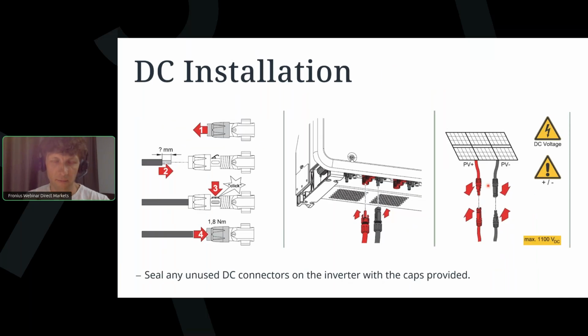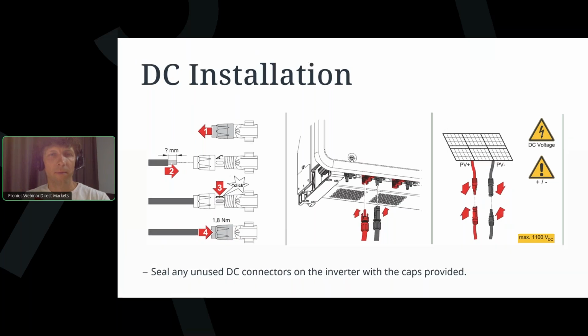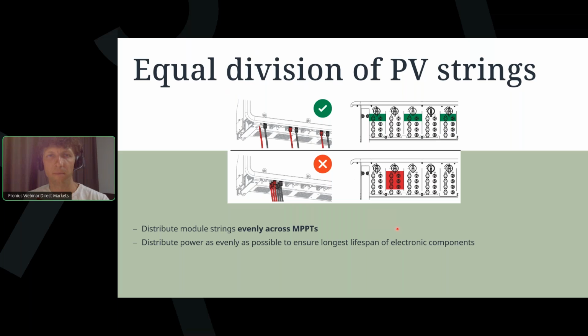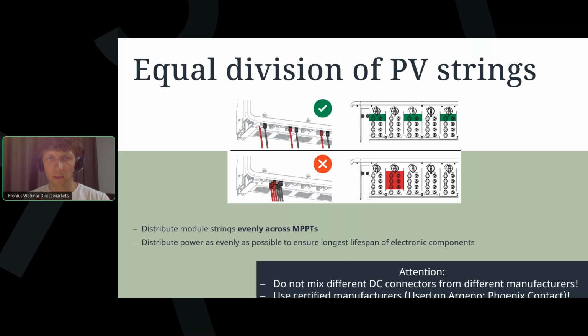About DC installation, don't mix plus and minus, of course. Correctly install wires with plugs. If you have more strings, split them into equal places. Don't put all strings on one MPPT. It helps your inverter last a long time. And of course, don't mix different DC connectors and different manufacturers for these connectors. Use the same as on the inverter.